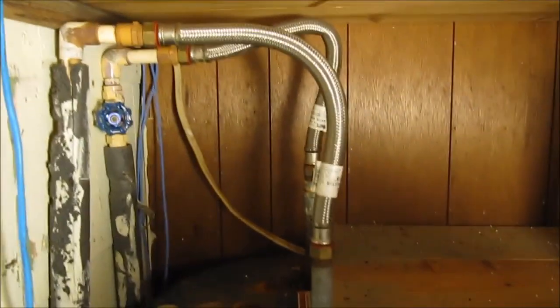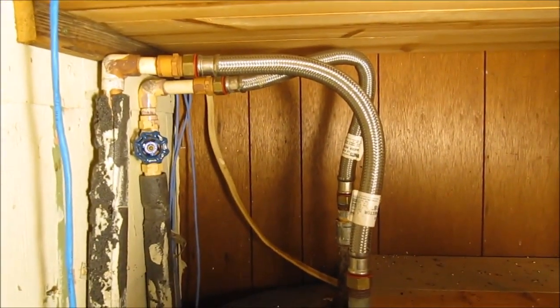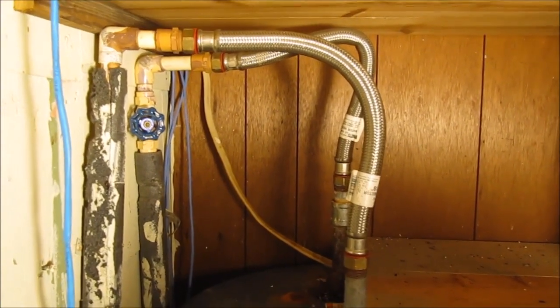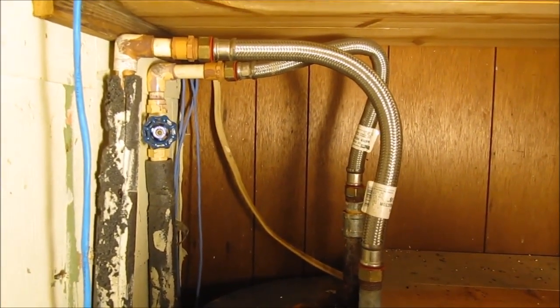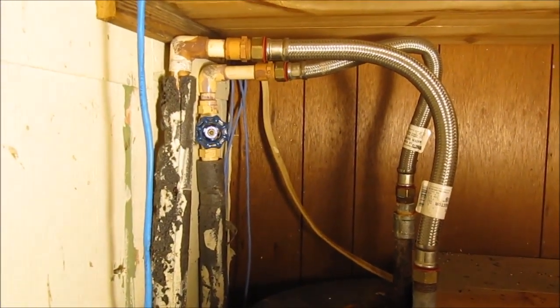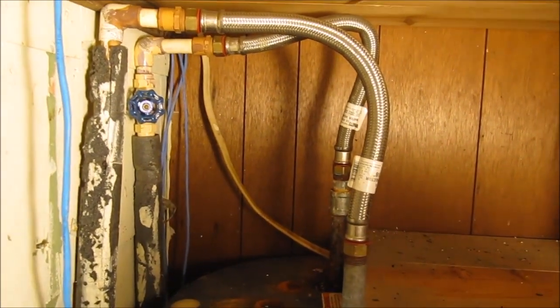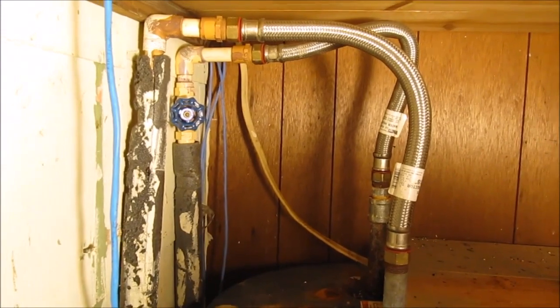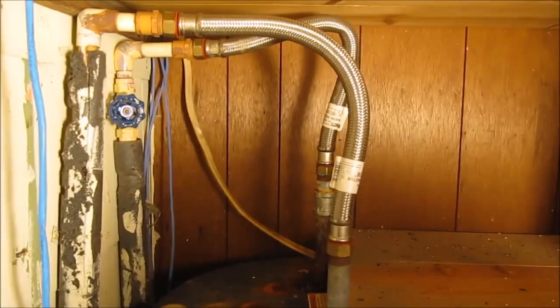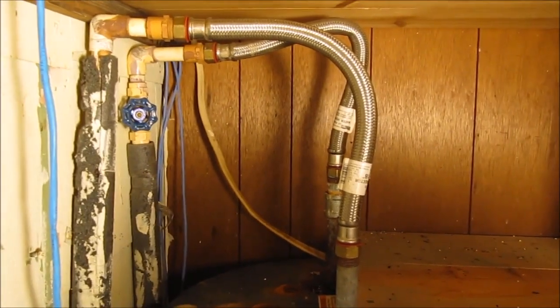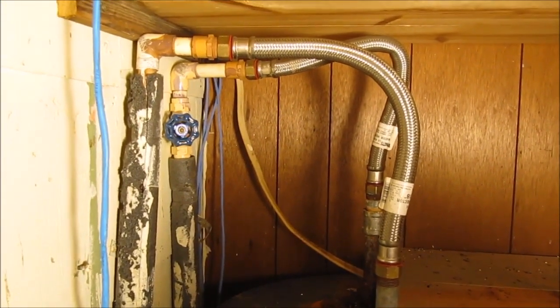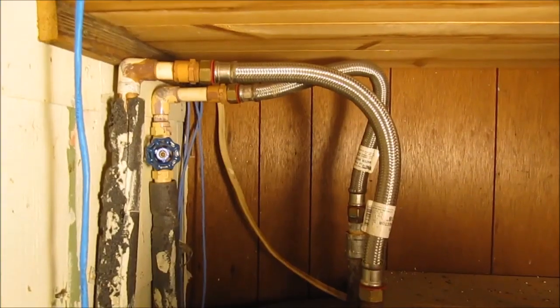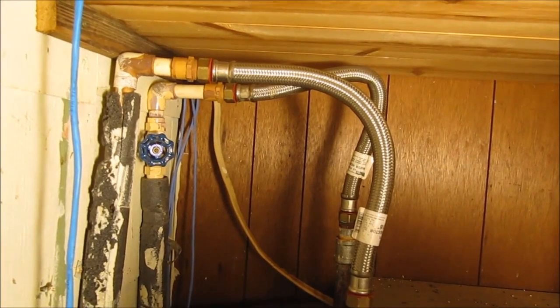I'm going to put it in place of this tank and use the 30 amp, 10 gauge wire that's already run here. Putting in an EcoSmart 8 would require me to run 8 gauge wire all the way from the breaker box. Since this 30 amp wire is already here, I'm going to see if I can put a 6500 watt tankless water heater. Today I'm only testing the 4500 watt water heater. I've got the thermometer and have to make some hoses to go from three-quarter inch to half inch female NPT.